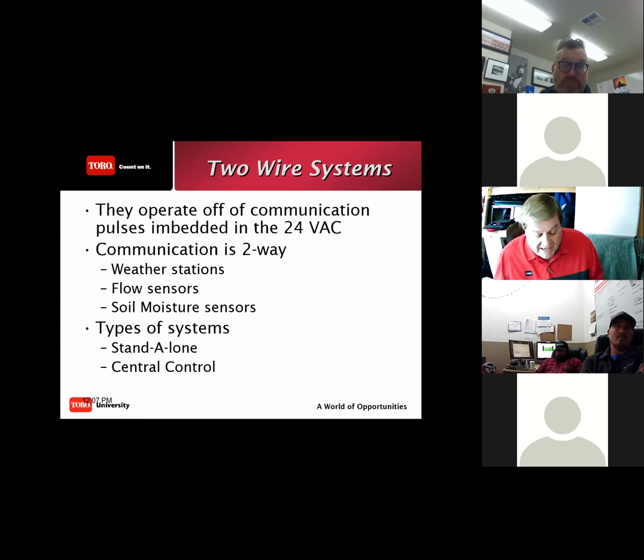Now, communication is always two-way, meaning the clock knows the decoder got the information. The decoder responds back to the clock: "Hey, we're good to go. We're going to operate it." The decoder, the little mini controller, as I mentioned, is out in the field. It can be hooked up to valves traditionally. It can be hooked up to moisture sensors to tell how moist the ground is. It can be hooked up to a flow sensor to let you know water is running, or water is running when it's not supposed to. It can even be connected to weather stations. So there's a lot of different nuances to two-wire, not just valves.